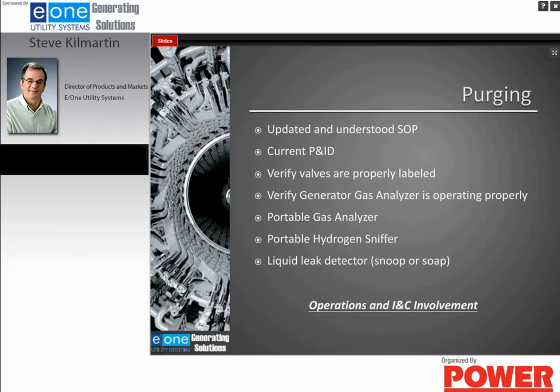And the reason I'm saying updated and current is because when I first got into this business, we would purge a generator every 18 months, every 24 months. The outages were more frequent. Now outages are going 5, 7, 10 years. So the person that purged that generator 10 years ago might not be with the company anymore. We are all aware that the pool of skilled labor is getting much smaller in the utility business, and we're also aware that power plants are cutting back on people. And with this, we're losing skilled people. So it's very important that you have, again, an updated and understood standard operating procedure, and that the P&ID is current, that nothing has been added to the P&ID, such as switches or transmitters or gauges. You need to make sure that they're on the P&ID and you know where they are.